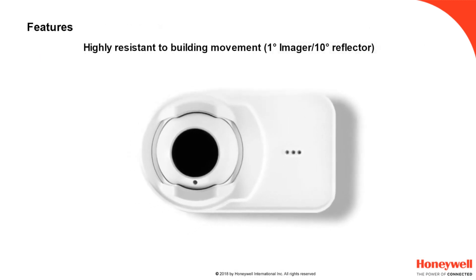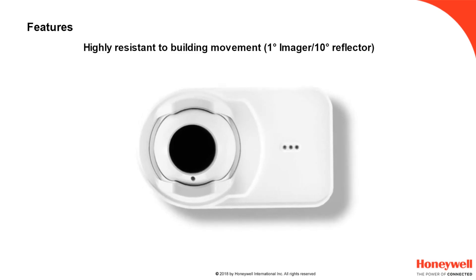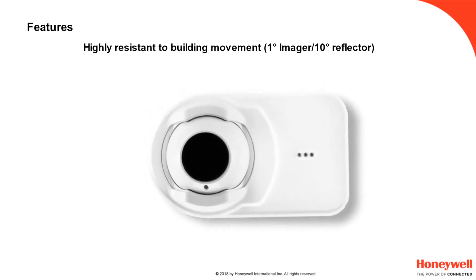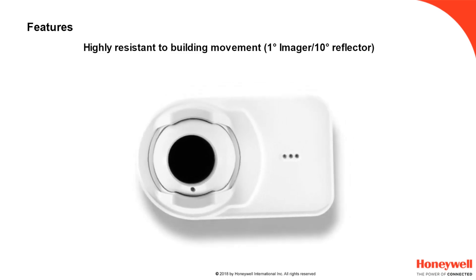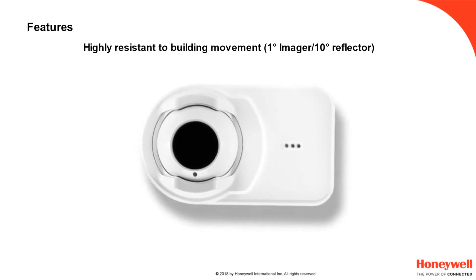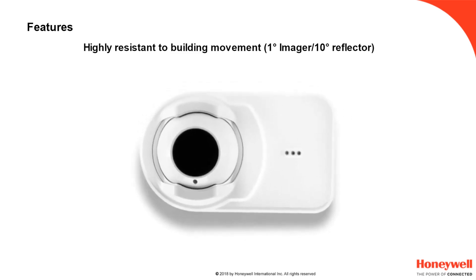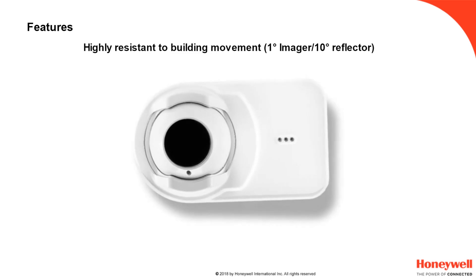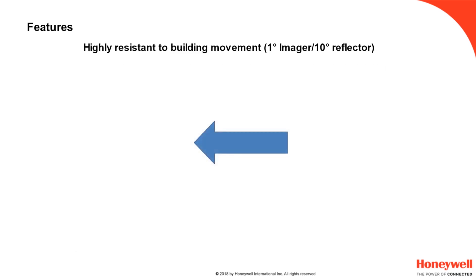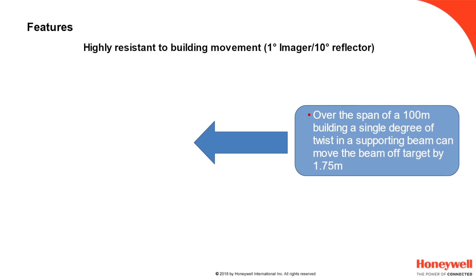The number one issue that beam detectors face is building movement, particularly thermal expansion, contraction and twist within metal-framed factories and warehouses that are a common site for beam detection. The OSID R can accept up to 1 degree of movement in all directions at the detector and 10 degrees at the reflector. At 330 feet or 100 metres, 1 degree of flex at the emitter or detector results in a shift of 5¾ feet or 1.75 metres about its centre.